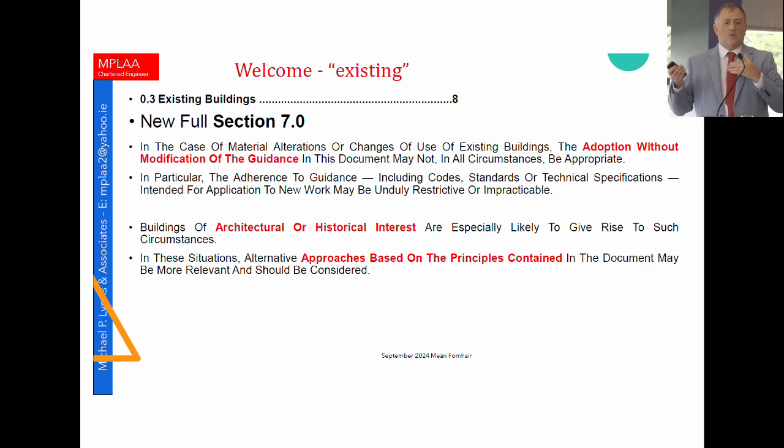Well, if you were to raise the ceiling to 15 meters high, what's the compensation that you can get for going from a 2-meter high ceiling and 18 meters in a dead end, to a 15-meter high ceiling? The TGDB doesn't give it to you. And Section 7 doesn't give the assessor any guidance either as to how to do it. 9999 does. You can increase the travel distance by 15%. You can reduce the effective width by 10 or 15%. But the TGDB doesn't, and Section 7 doesn't.